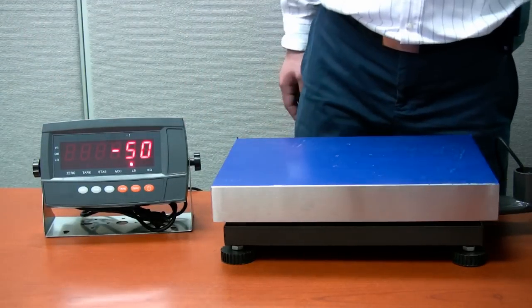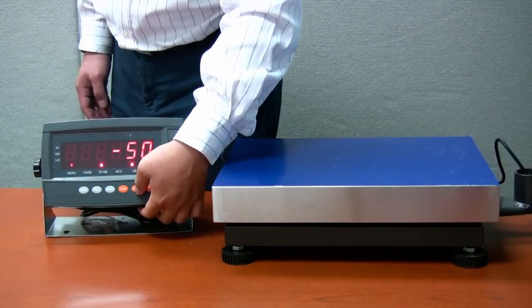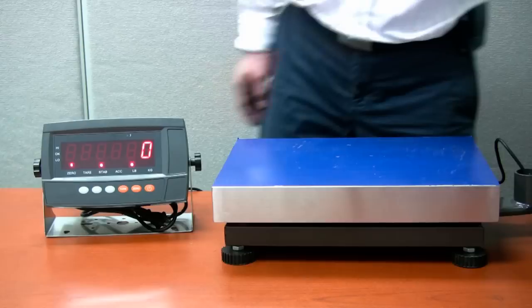The indicator will go to weighing mode and show zero. Remove the calibration weight and zero out the scale and the scale is ready to use.